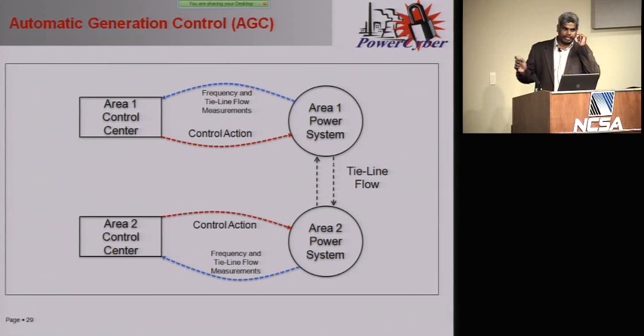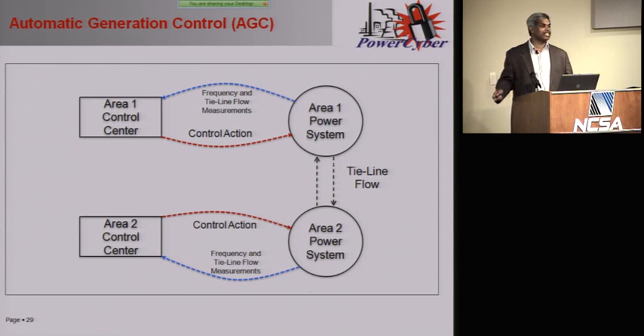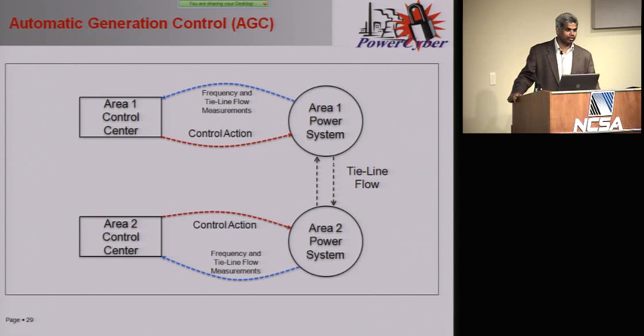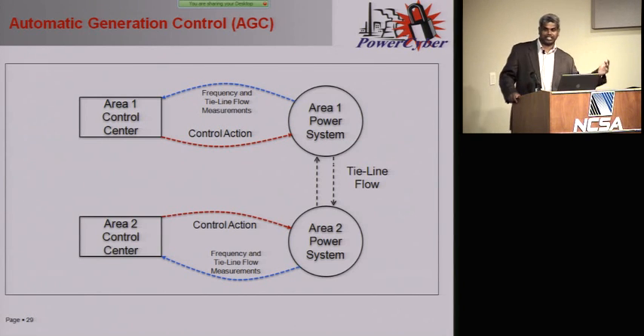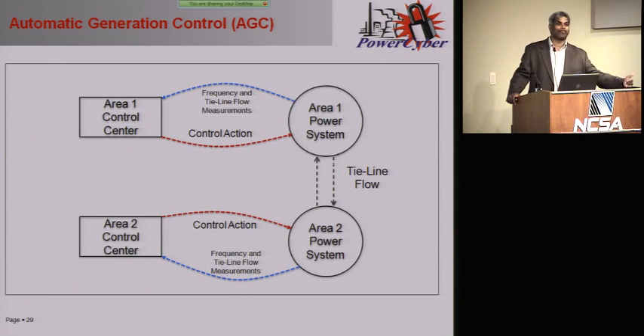So I'm going to show an example through a data integrity attack. This measurement comes from the cyber system. If somebody manipulates the tie line measurement or frequency measurement, that will result in the AGC taking a wrong decision. For example, whenever generation should not be increased, it will end up increasing the generation, which will result in increasing the frequency of the overall system, exceeding the NERC reliability criteria, eventually leading to problems in the system. That's what I'm going to show.